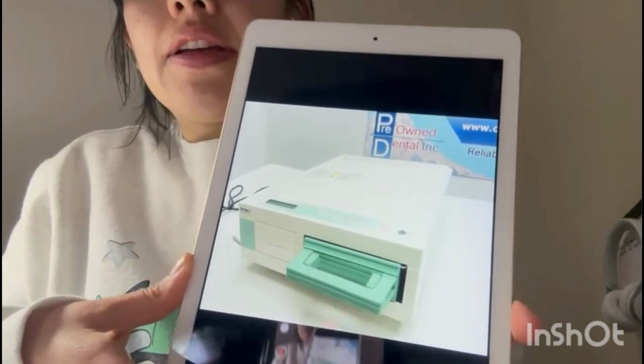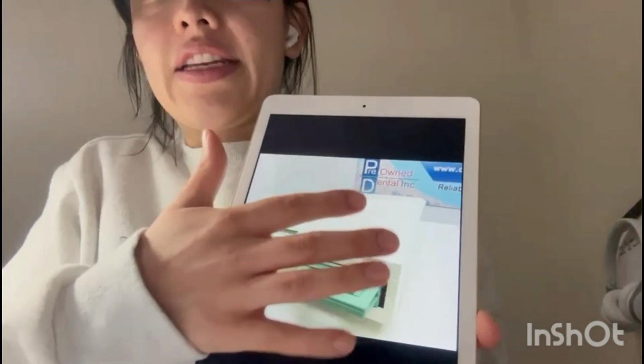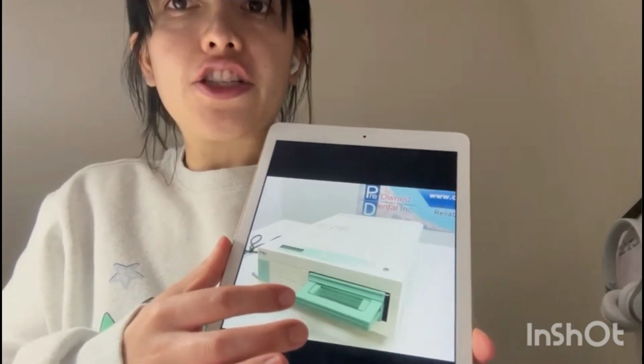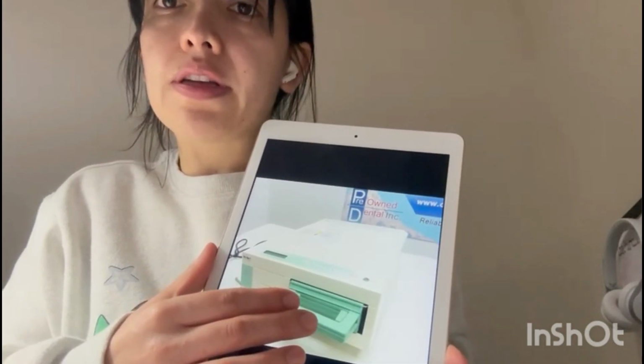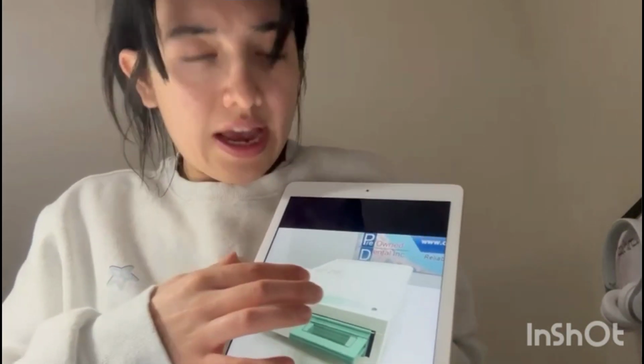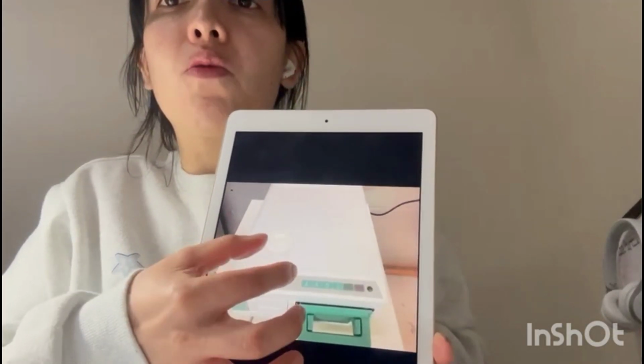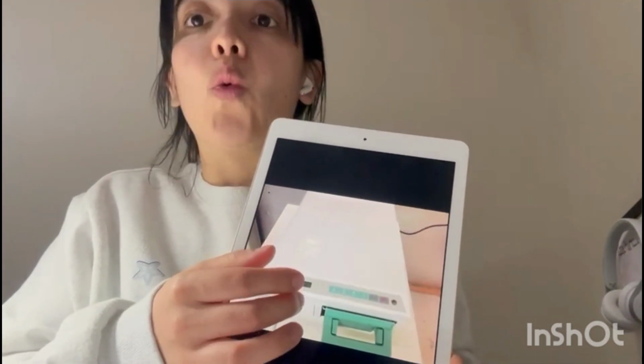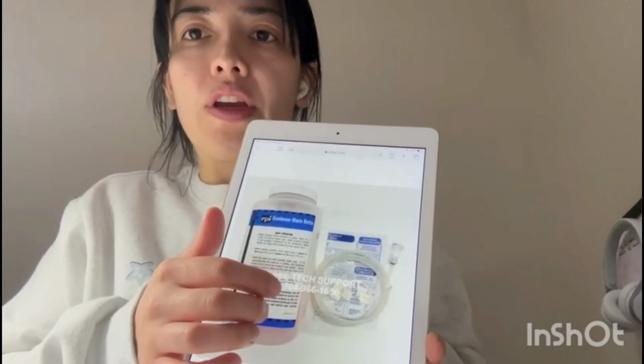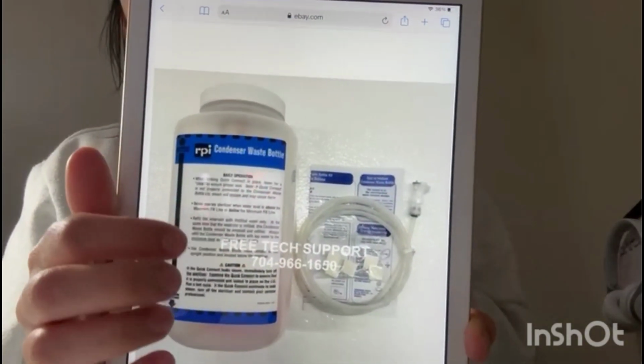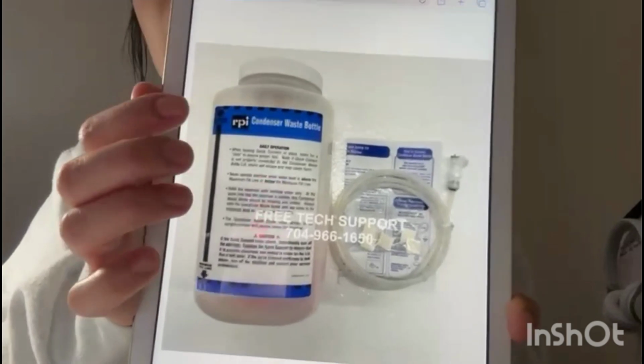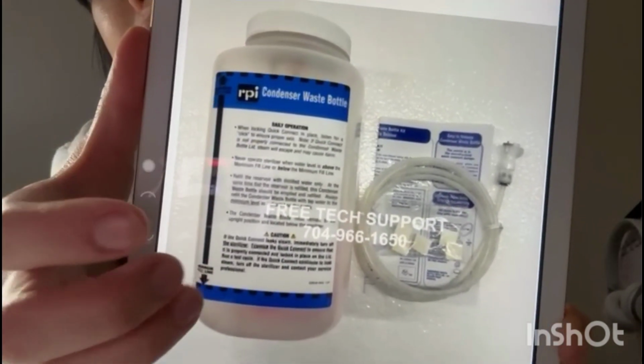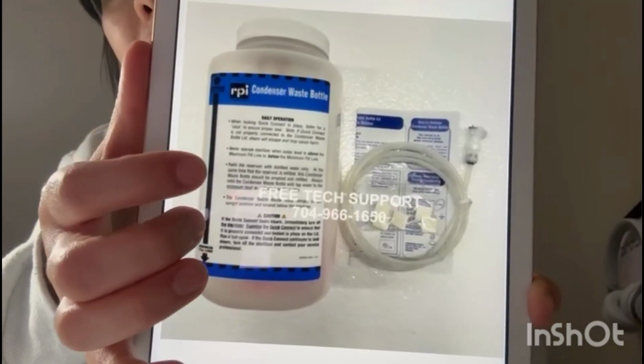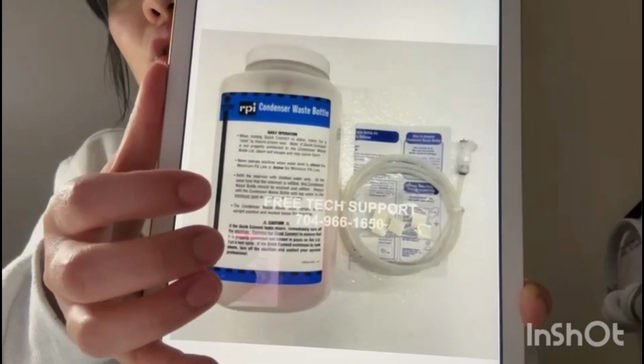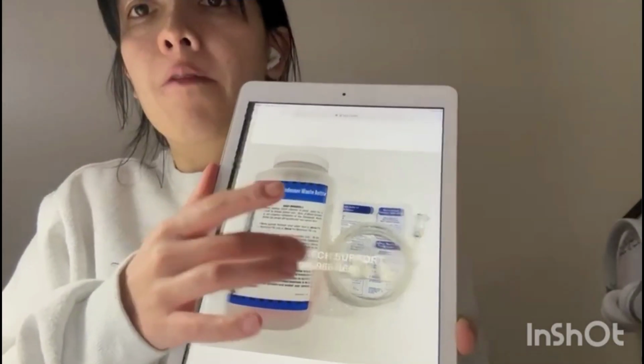This is the Statim. As with any other sterilization machine, we have our cassette where we're going to place all the instruments, as well as where we are going to put the water in. Here we place only distilled water, and it goes into this bottle. This condenser has 2 different lines, and for the Statim, the water needs to be between these 2 so it is able to work.